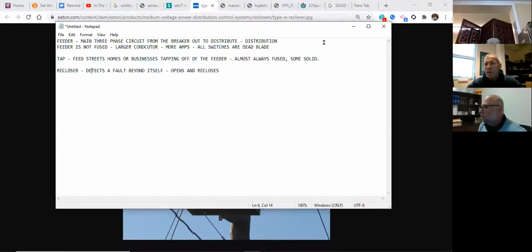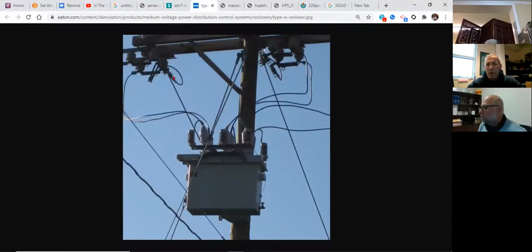So say I've got, we'll go back to this picture right here, say on the line coming into the switch from this side. Remember I said it detects faults beyond itself, and there's a fault on this sectional line going beyond itself, further down, inbound here, outbound here. It detects a fault, it's going to open, reclose, open, reclose, open, reclose, if the fault remains. Now, inside this box, I can program it: if it opens 3 times, I don't want to reclose anymore. 3, 2, 5, 10, 1, whatever you want to program it to. It just does not have all the brains that a breaker does in a substation.